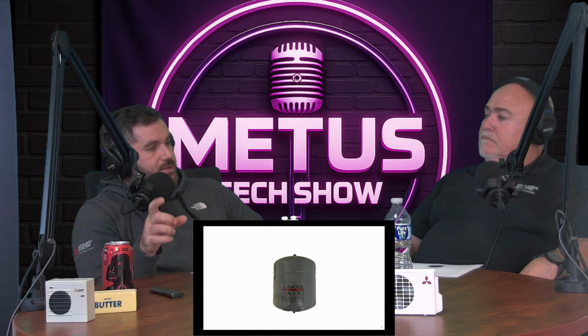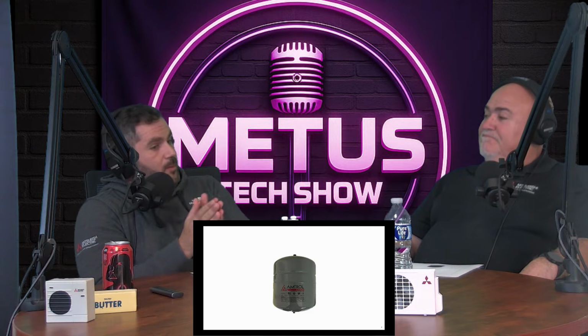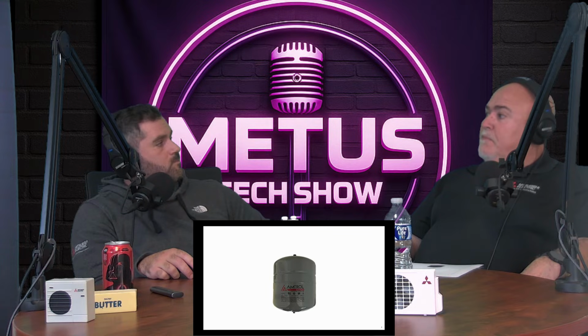Now, the purpose for it is that when you heat up water, it will always expand. Yeah. Warmer water is going to expand. So what this does is allow for that thermal expansion without building system pressure, right? Because without an expansion tank, when the water expands when it's heated, it will build pressure in the system. The actual system pressure will increase. This will prevent that. It'll keep that pressure the same, because really what it's doing is just compressing down on that bladder. Yeah, and the system can, number one, be dangerous without an expansion tank. Very dangerous. Right? It's a pressure vessel, so it's essentially a bomb at that point.